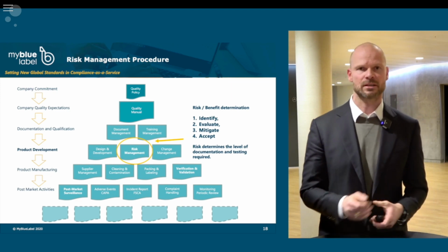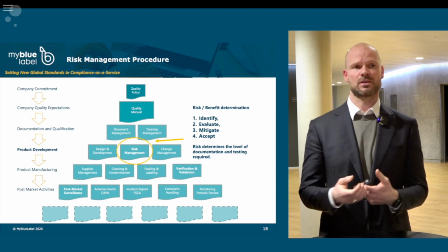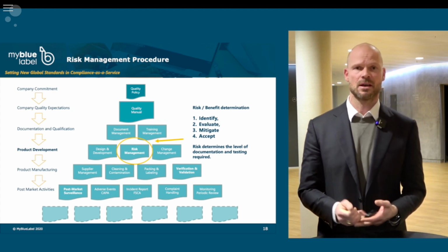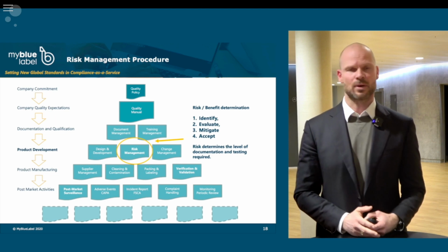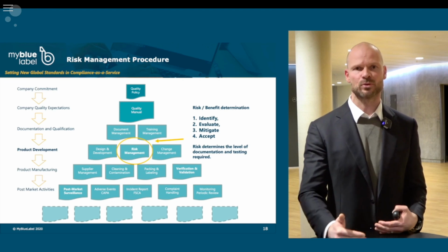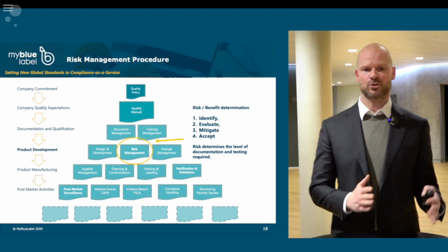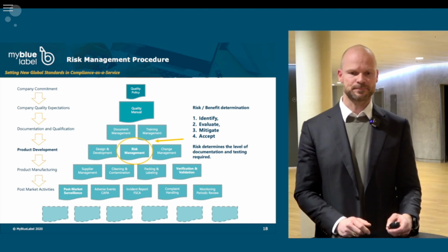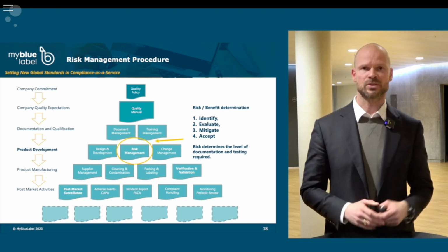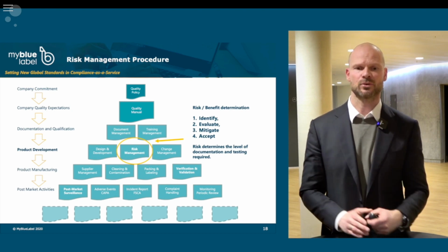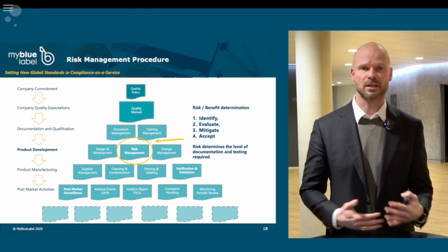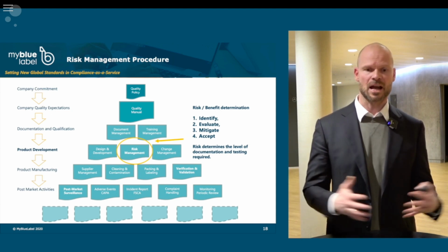But working with risk, it's about identifying a risk, it's about evaluating the risk, it's about risk controls, and then in the end you need to accept the risk. And these steps are quite similar no matter which industry you're in, but this is the approach and the processes that you need to take to identify the risk for the device. So it's something that you need to focus on as soon as you have the right documentation, management procedures, and also your training. Then please look into what is your risk in your device development, and also in your surroundings, supplier risk, and so forth.